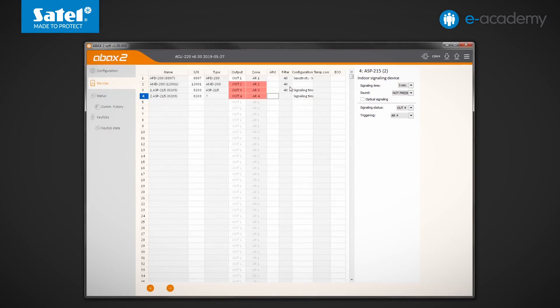The next column is designated filter. It refers to the function of controlling the presence of radio devices in the system. The value entered here defines how many communication periods without contact between the controller and device must pass before loss of communication is reported.